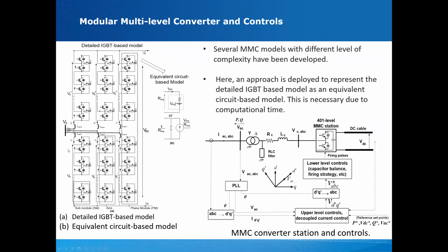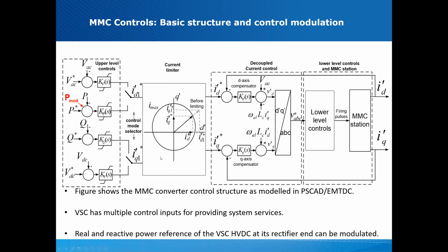In PSCAD, we have the capability to model detailed IGBTs, whereby you represent the converter down to the switching level. We also have the capability to have an equivalent circuit-based model, which still has all the sub-module representation, but you don't have to model all the sub-modules in detail. So we would say a Thevenin equivalent circuit-based approach. MMCs and all forms of converters can be modeled down to the switching level. Here, as an example, we've modeled the MMC, but what I'm interested to show you is that when we have weak grid conditions, we may need to allow these converters to provide system services.